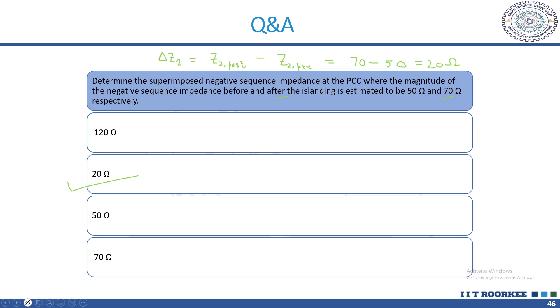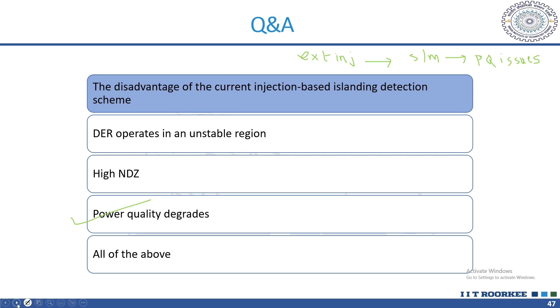Then the disadvantage of current injection based islanding technique scheme is: DER operate in unstable region, high non-detection zone, degradation of power quality, or all of the above. So here you are externally injecting some signal, right? So that will interfere with your system, which may lead to degradation of your power quality. So these types of islanding detection techniques basically face power quality degradation issues.